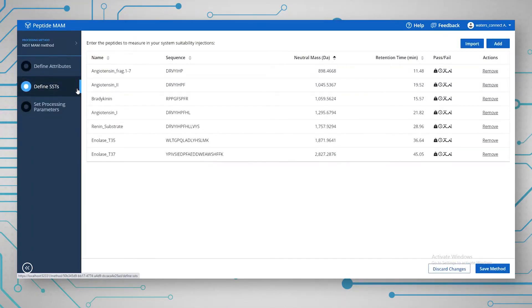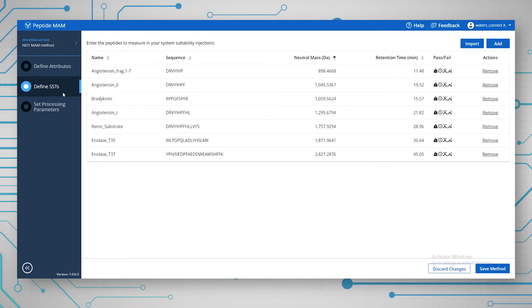Another part of this workflow is the system suitability test. What that allows you to do is use your SST samples to monitor the status of the instrument. For example, if you wanted to make sure that the mass accuracy, response, and intensity of peaks were consistent across the run — ensuring you weren't losing instrument performance — this is a really good way to monitor the instrument, so that any variability within your unknown samples is down to the samples and not the instrument.